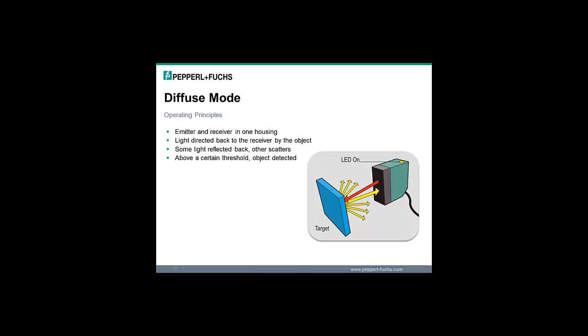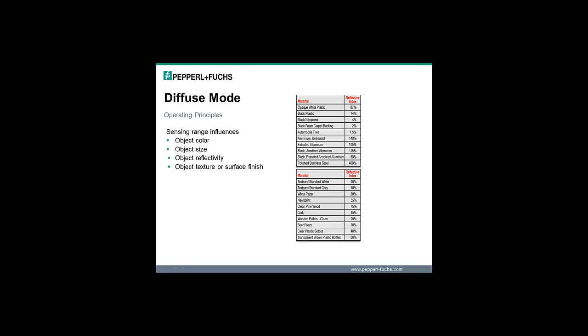Diffuse mode sensors have both the emitter and receiver elements in one housing. Light from the emitter is directed back to the receiver by the object. The object reflects some light back to the sensor and scatters the rest. The object is detected when the light at the receiver is above a specified threshold. Diffuse mode sensors detect objects solely on the energy or intensity of the reflected light. If an object is in the right spot and is reflective enough, then it will be sensed; if not, it won't be sensed.